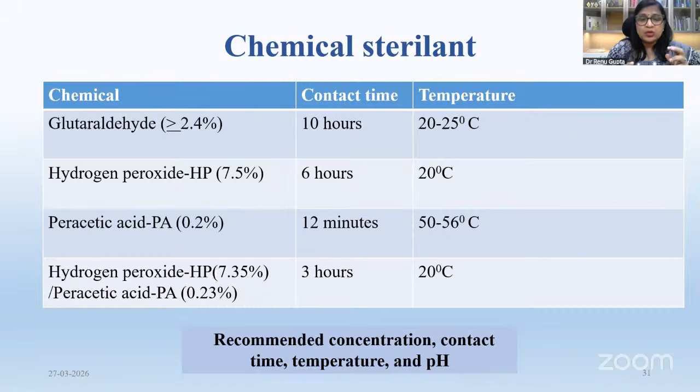Then it brings about sterilization, if it is able to penetrate. If your sterilant has not entered into the channels of the endoscope, it will not bring about the activity. So contact time is very important. The same chemical can work as a sterilant or as a high level disinfectant depending upon the concentration used, contact time, temperature and pH.